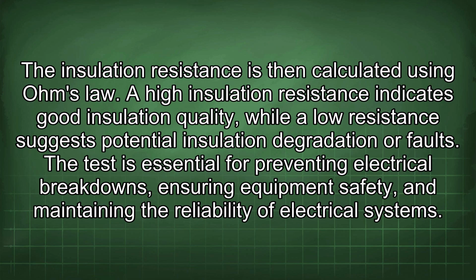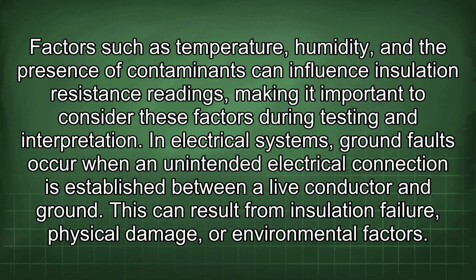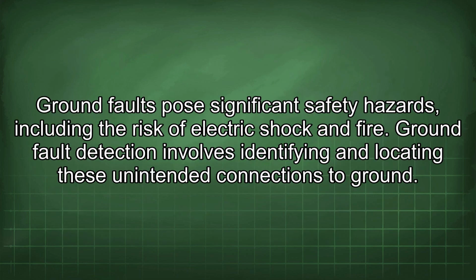A high insulation resistance indicates good insulation quality, while a low resistance suggests potential insulation degradation or faults. The test is essential for preventing electrical breakdowns, ensuring equipment safety, and maintaining the reliability of electrical systems. Factors such as temperature, humidity, and the presence of contaminants can influence insulation resistance readings, making it important to consider these factors during testing and interpretation. In electrical systems, ground faults occur when an unintended electrical connection is established between a live conductor and ground. This can result from insulation failure, physical damage, or environmental factors. Ground faults pose significant safety hazards, including the risk of electric shock and fire.